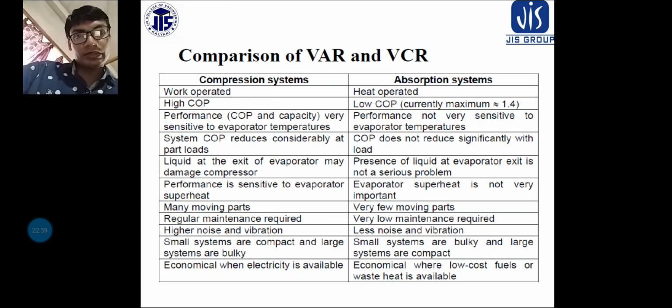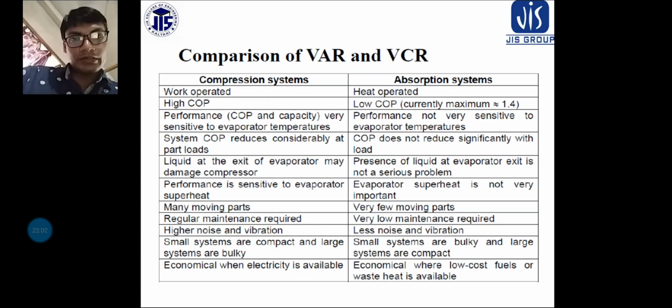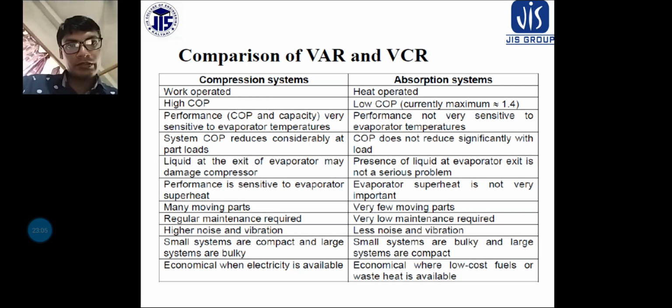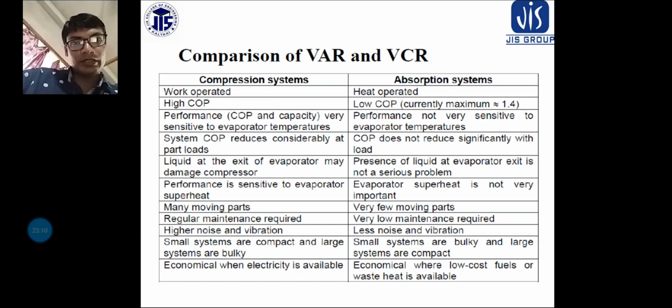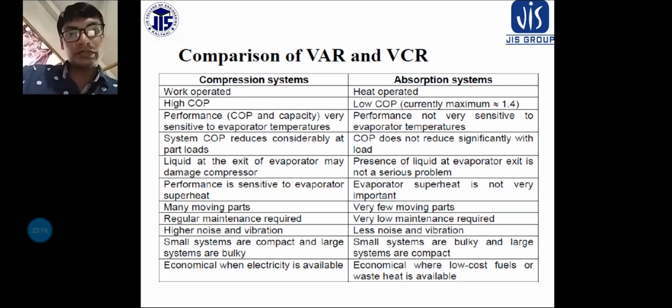Performance is very sensitive to evaporator temperature. So the performance, meaning your COP, coefficient of performance, and capacity, is very sensitive to evaporator temperature, while in absorption systems the performance is not very sensitive to the evaporator temperature. Okay, next is point number 4. The system COP reduces considerably at part loads. So the system COP reduces at part loads.